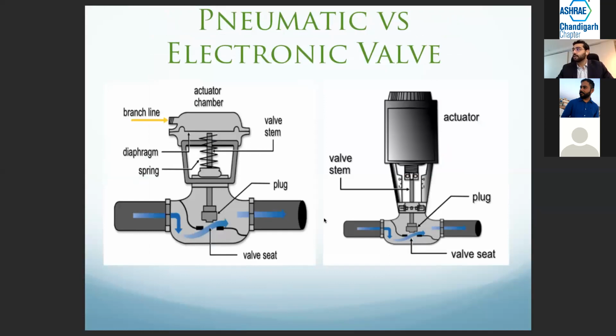So we'll do an example of pneumatic versus electronic valves. You can see in this case, the valve is being controlled by pressure. There's this branch line that we saw in the previous example. The pressure comes, the actuator chamber presses on the diaphragm and the spring, and slowly the plug starts moving down onto the valve seat. So the flow of the water is restricted. And this is how pressure is used to control the pneumatic valve.